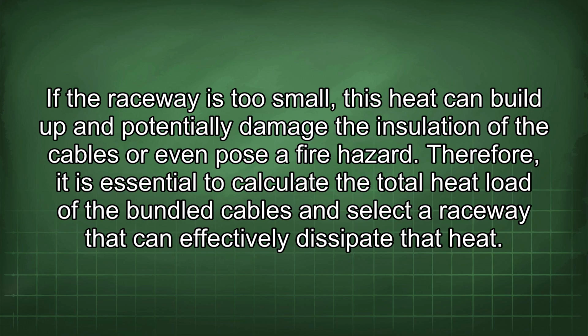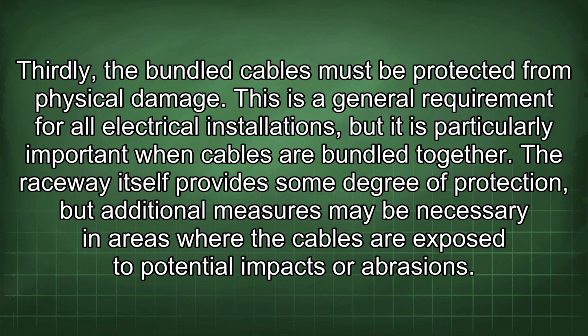Therefore, it is essential to calculate the total heat load of the bundled cables and select a raceway that can effectively dissipate that heat. Thirdly, the bundled cables must be protected from physical damage. This is a general requirement for all electrical installations, but it is particularly important when cables are bundled together. The raceway itself provides some degree of protection, but additional measures may be necessary in areas where the cables are exposed to potential impacts or abrasions.